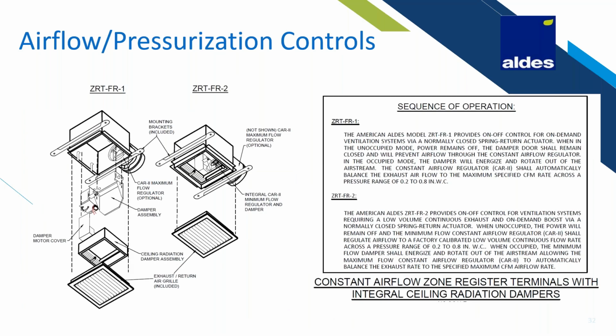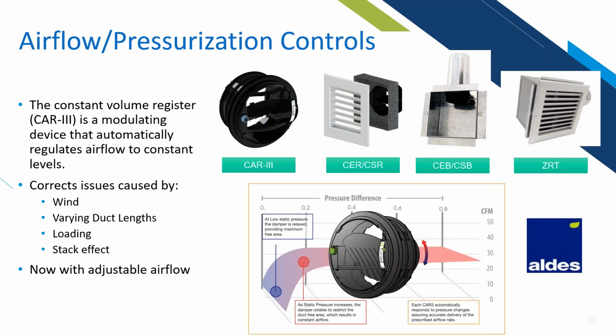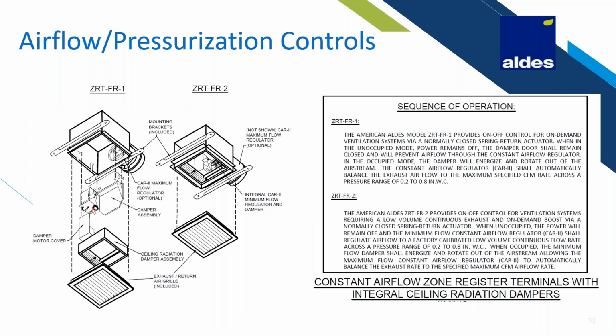And the way that works is, here's an example of our fire rated version. By the way, all of these units can be fire rated, the boot, the register, or the ZRT. The difference can be seen here. You can see the damper assembly. When the damper assembly closes, you shut off airflow to that unit, and when it's open, you're getting the flow from the constant airflow regulator in the neck. Alternatively, with a ZRT2, when that damper closes, you're getting the airflow in the damper, which will be your minimum airflow, and then when it opens, you'll be getting the maximum airflow. So this can be used for demand control ventilation in a riser type design.